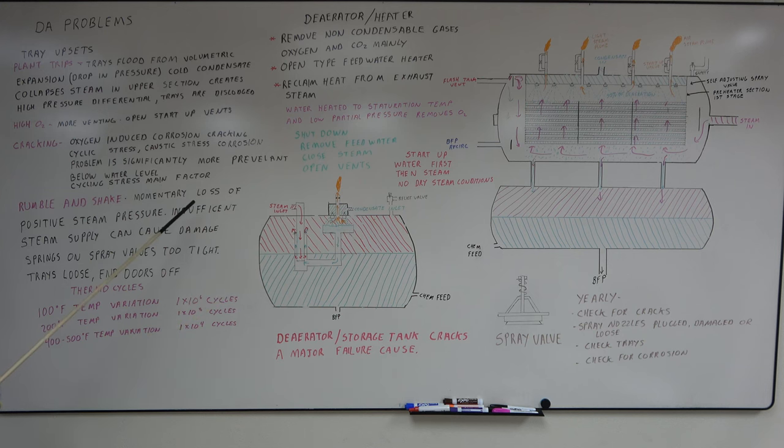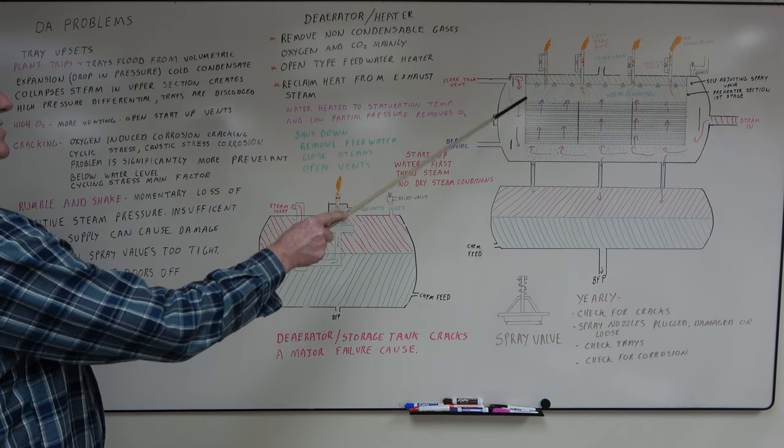Rumble and shake. It can be a momentary loss of positive steam pressure. It can be insufficient steam supply. It can cause a lot of damage to the deaerator. Springs on the spray valves too tight can be a problem. Trays loose and doors off. We're talking about the spray section here. They've got doors.